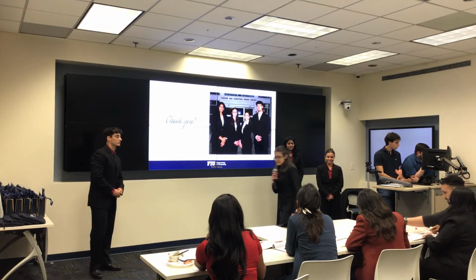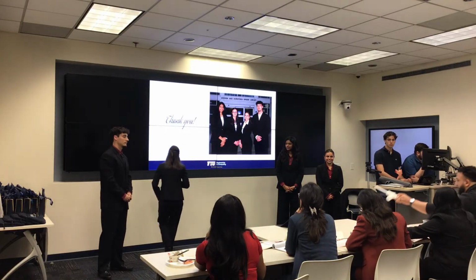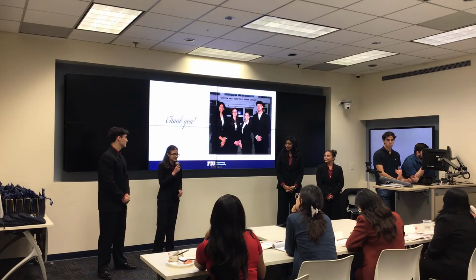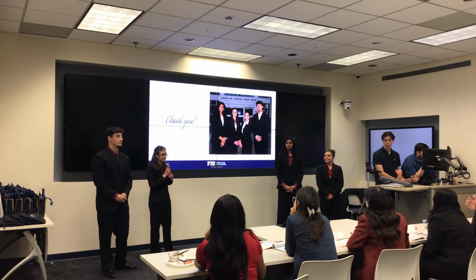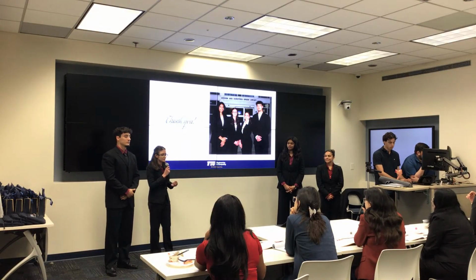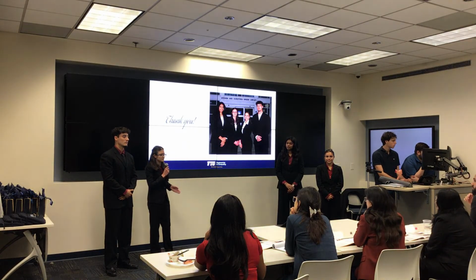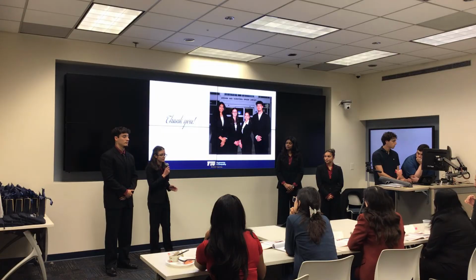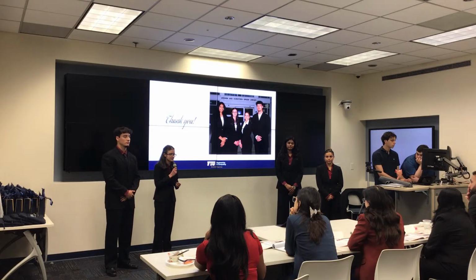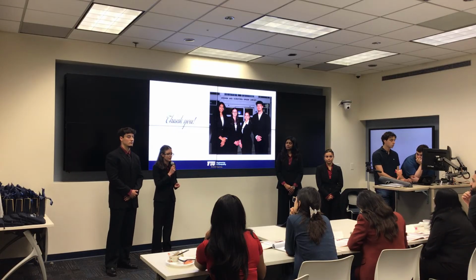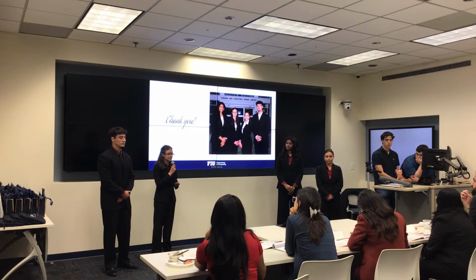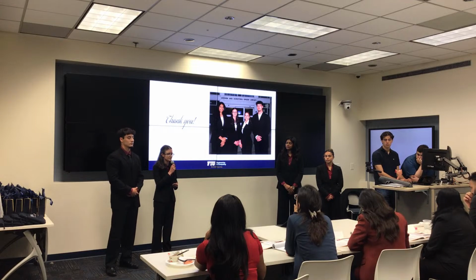Thank you. So as I said previously when I was explaining the probe, the displacement is held constant, so what's changing is the pressure needed to displace the tissue. That pressure is going to depend on how stiff the tissue is, so if the tissue is really soft, for example, it's going to require less pressure to deform it. So that's how we correlate that negative pressure that's required into the cervical stiffness value.